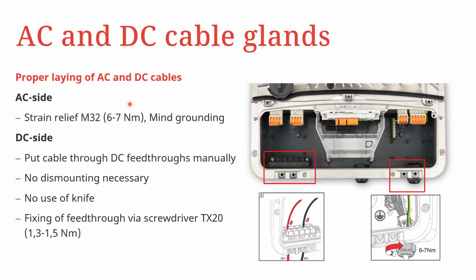For the AC and DC connection area, we have provided the cable glands, and for the AC area, we have an M32 cable gland, which can be tightened to about 6 to 7 Newton meters. And then for the DC area, you have the cable feed-throughs where you put through the cables, as we can see here. So you do not need to take the DC connection area out to fit the cables through.